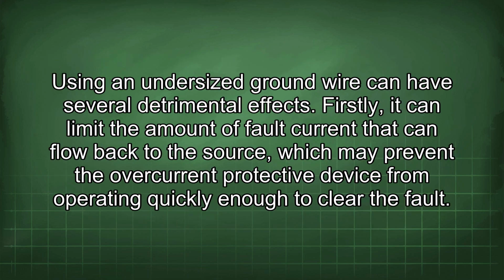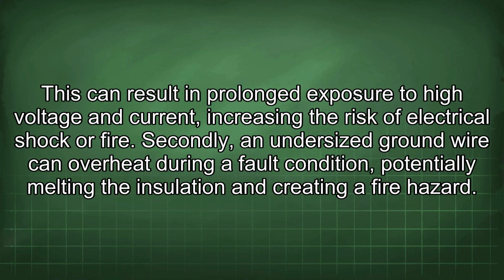Using an undersized ground wire can have several detrimental effects. Firstly, it can limit the amount of fault current that can flow back to the source, which may prevent the overcurrent protective device from operating quickly enough to clear the fault. This can result in prolonged exposure to high voltage and current, increasing the risk of electrical shock or fire.